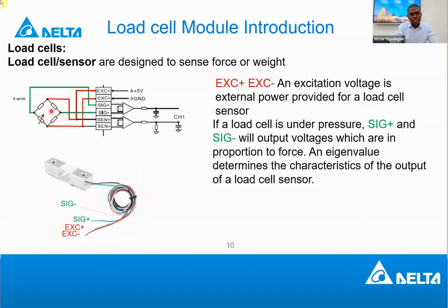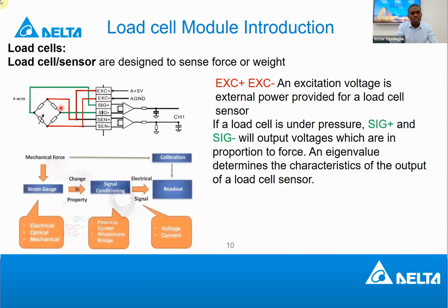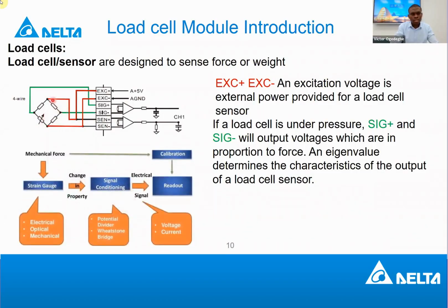And then there's internal circuitry in the cell. If it receives 5 volts from the load cell module, this internal circuitry will amplify the small signal to a bigger voltage that will be read at the output. This output is what the load cell module of the AS PLC takes. Then it converts it to a digital value, and based on that digital value, you can now control your machine. This is just the picture representation of how this load cell works.